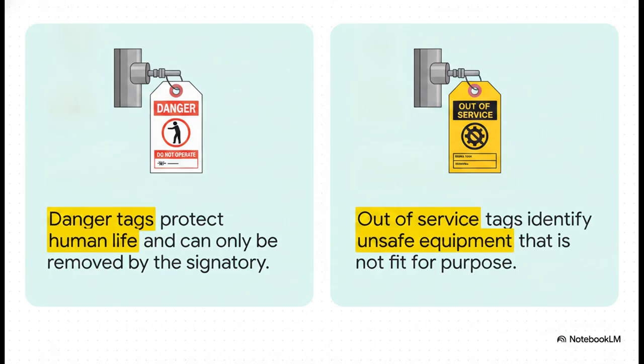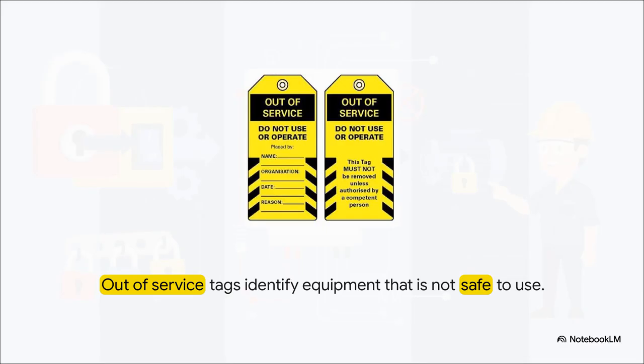On any professional job site, you've got to recognize a crucial distinction: the difference between a danger tag and an out-of-service tag. It really just comes down to what we are trying to protect. Danger tags, which are always red, black, and white, protect human life. Out-of-service tags, which are yellow and black, these simply protect broken or unsafe equipment. To put a really fine point on it, an out-of-service tag can be removed by any competent person once they have repaired the defect. But a danger tag? That is sacred. It can only ever be removed by the person whose actual name and signature are written right there on it. It is a personal, physical guarantee that returning power will not endanger their life.